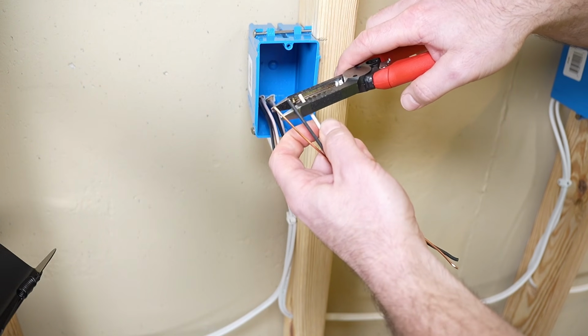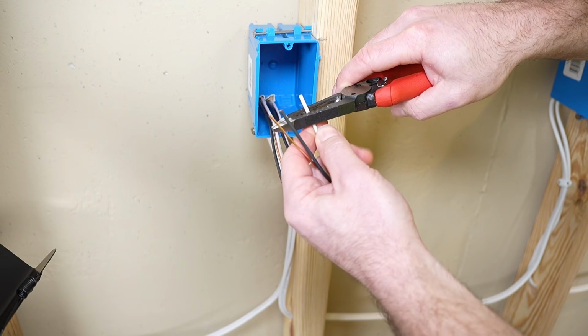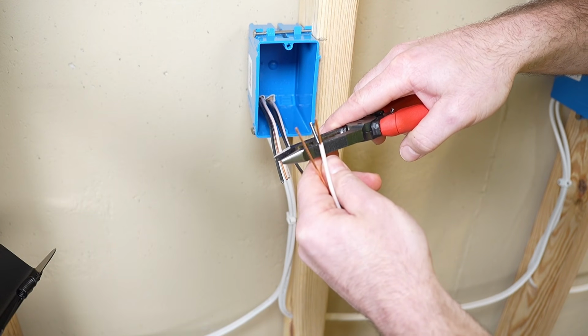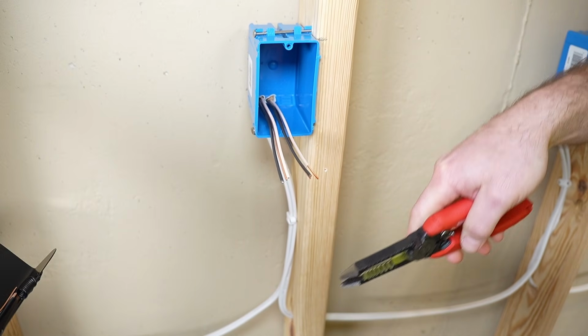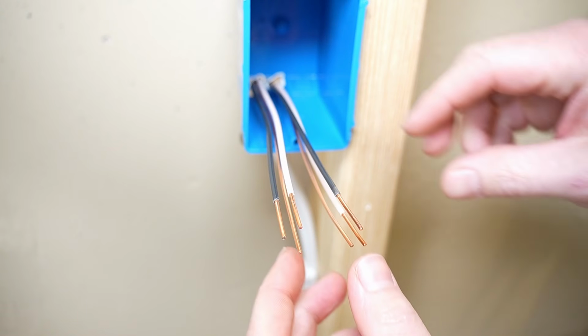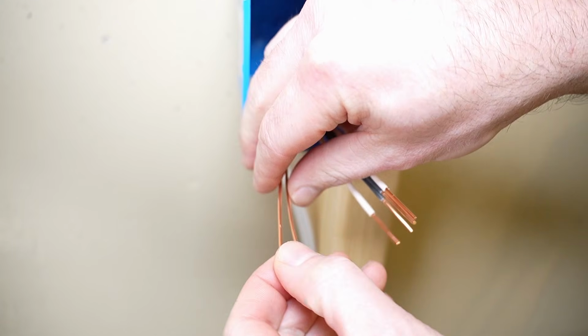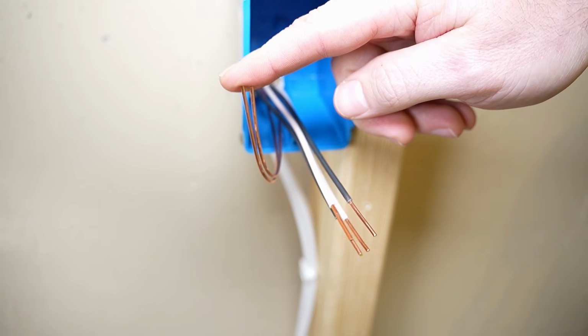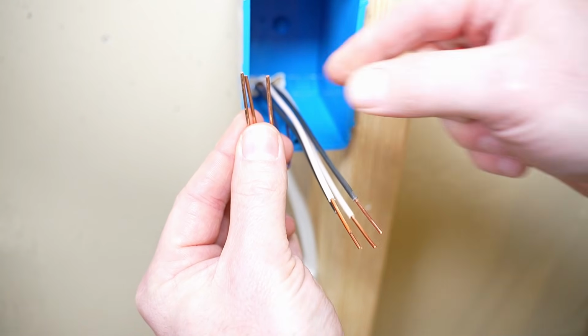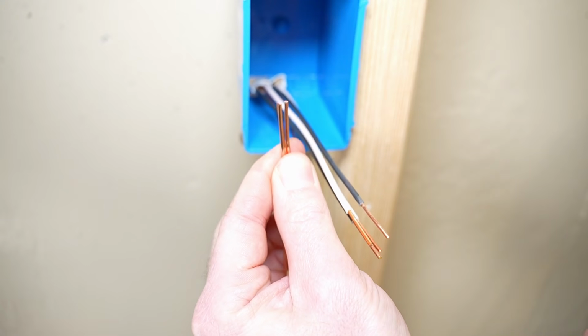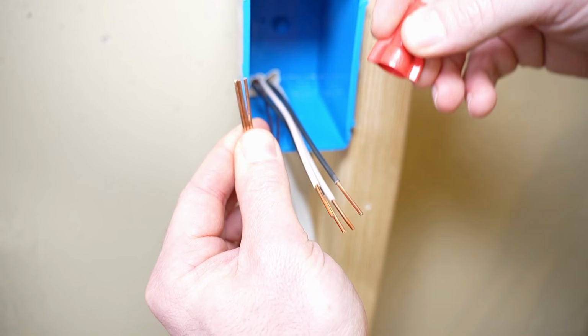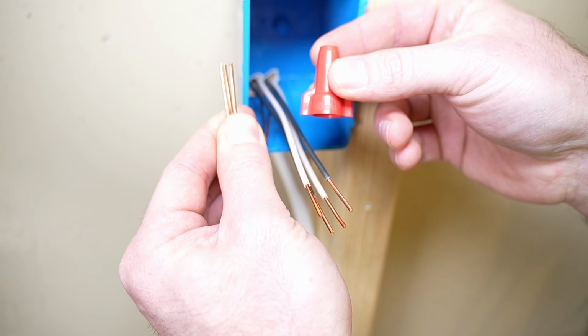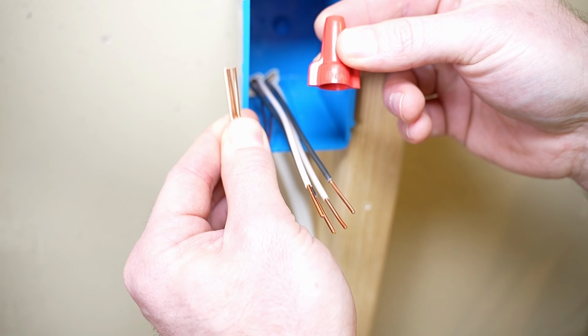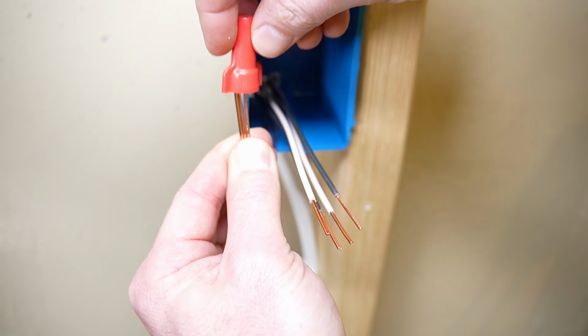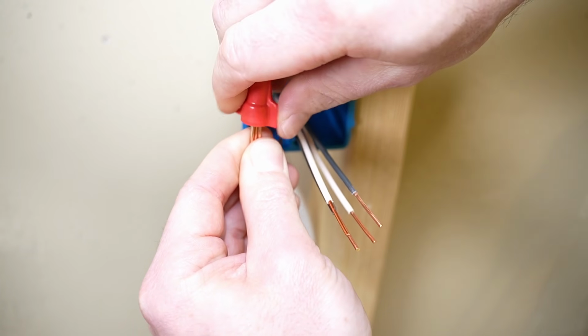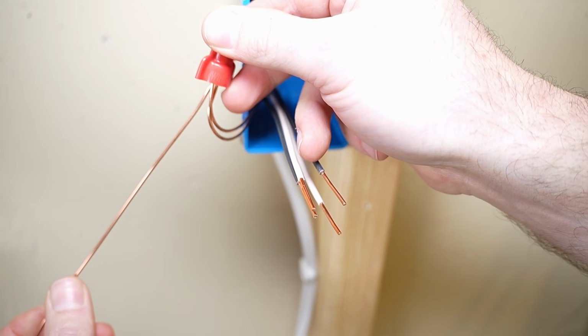I'm going to start by stripping out all of the wires, including these pigtails. We want to strip these out approximately to 5/8 of an inch. Now with everything stripped out, I'm going to grab these in pairs. I'm going to start with the ground wires, line them up, bring in our pigtail piece, line it up as well. And because these are all the same size and type wire, we're going to make them flush. If you want to learn more about using wire nuts, I made an entire video discussing wire nuts. Link in the description. So with everything lined up, we can simply start twisting our wire nut onto the ground splice. And there we go. The ground is pigtailed out.